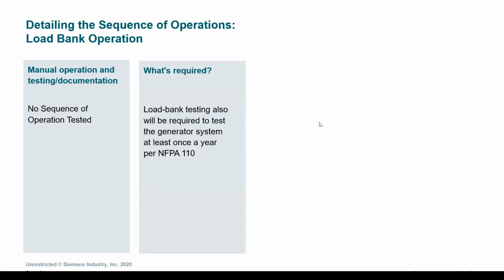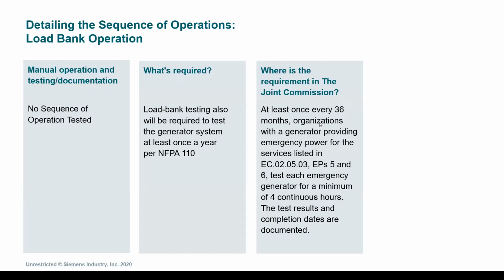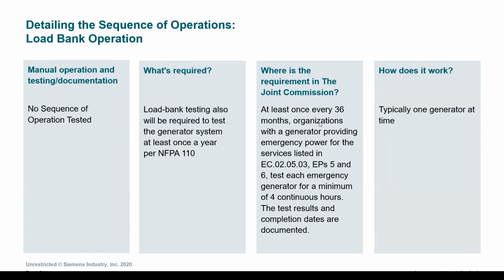The load bank is required to be tested per NFPA 110 at least once a year. Many of you know that it's also a requirement of Joint Commission, although Joint Commission indirectly requires it as part of their NFPA 110 compliance. They also specifically state in the section identified that it does need to be completed at least once every 36 months and for a minimum of 4 hours. Most often, when the load bank test is done, it is done one generator at a time to ensure that if normal source or utility power is lost during the load bank testing, the emergency system or the essential system in a hospital is never jeopardized.